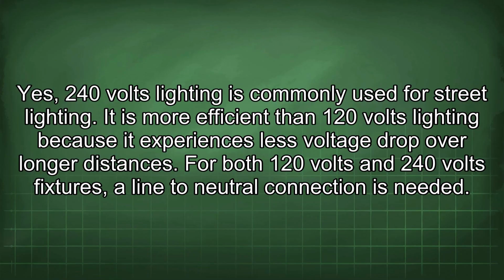Yes, 240 volts lighting is commonly used for street lighting. It is more efficient than 120 volts lighting because it experiences less voltage drop over longer distances. For both 120 volts and 240 volts fixtures, a line to neutral connection is needed.